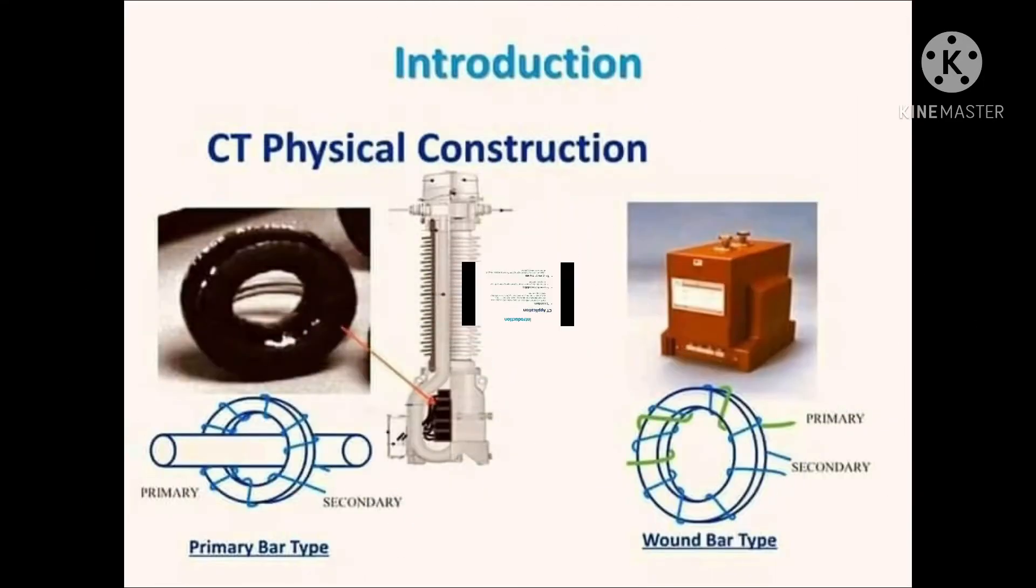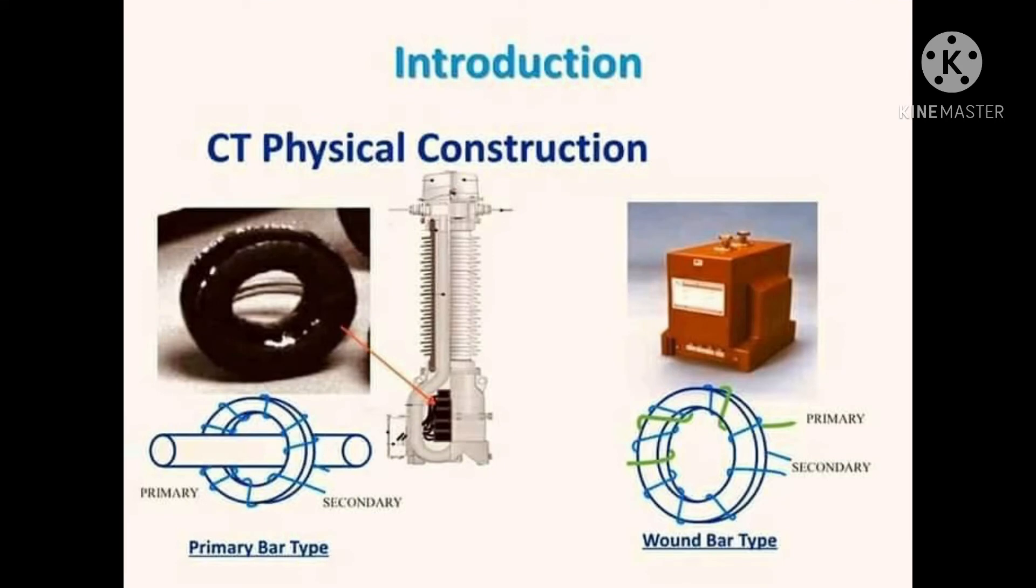Circuit current flows through its primary winding. When the current transformer works, its secondary circuit keeps closed. Therefore, the impedance of the series coil of measuring instrument and protection circuit are very small. The working state is close to short circuit.